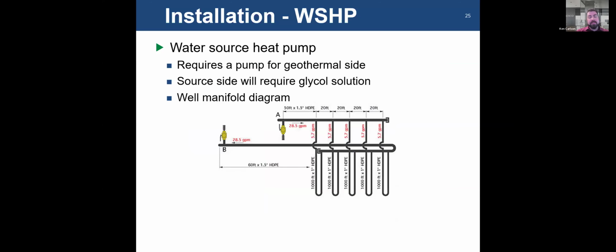Just a little bit of information on geothermal piping. When installing these systems, you'll have to have a glycol solution. All right, the temperature going back to the ground in heating mode could be below 32 degrees. You'll need a pump. All right. Typically these are manifolded together. If they're vertical wells, oftentimes they are piped in what they call a reverse return.